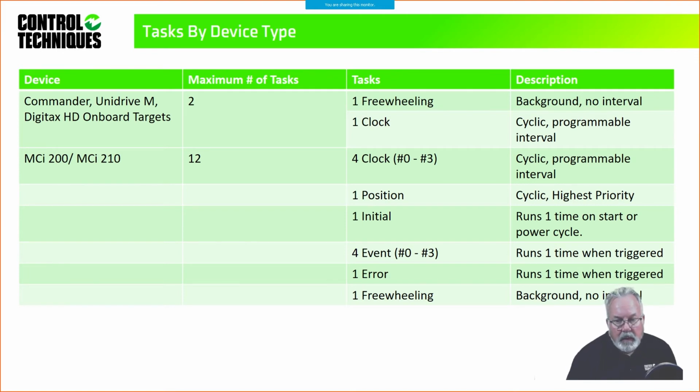The idea being that if you have a drive fail, you disconnect or unplug the MCI module, replace the drive underneath of it, and so long as you haven't changed the motor or anything like that, on initial power up, if you have your drive parameters in this task, now the end user won't need to open Connect and load his parameter file because it's here coded into a POU that's being operated by the initial task.